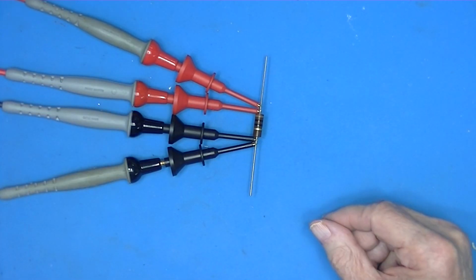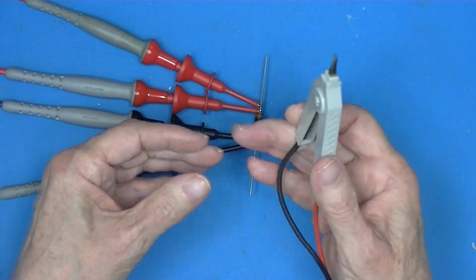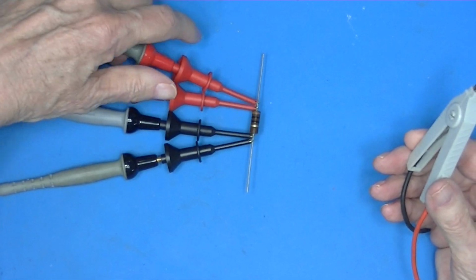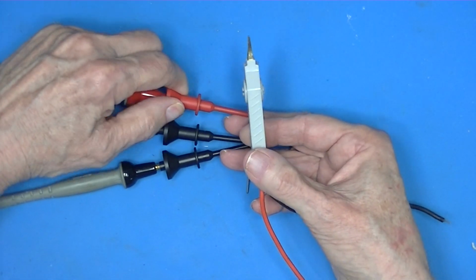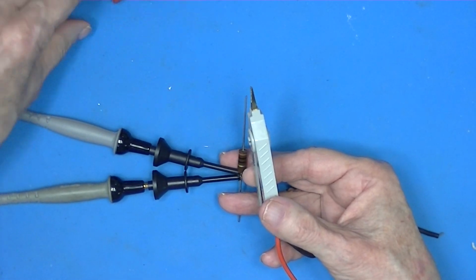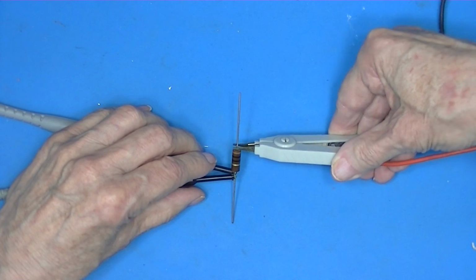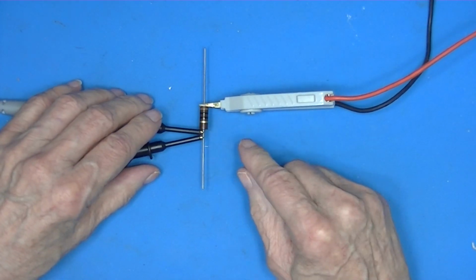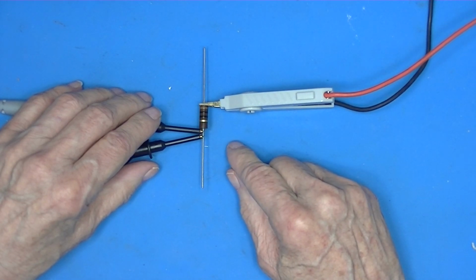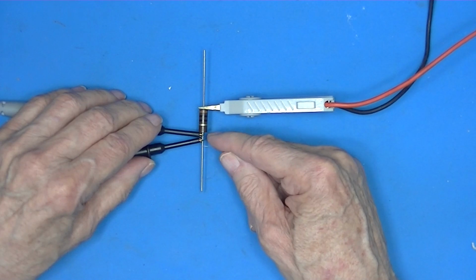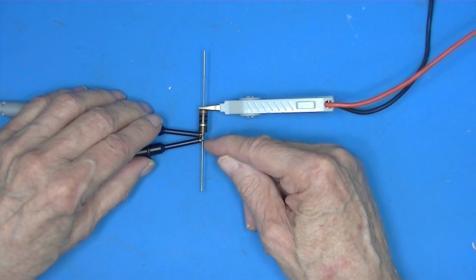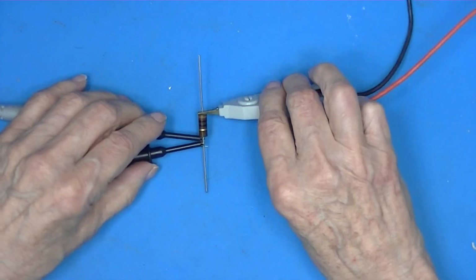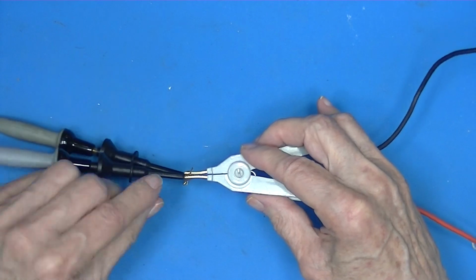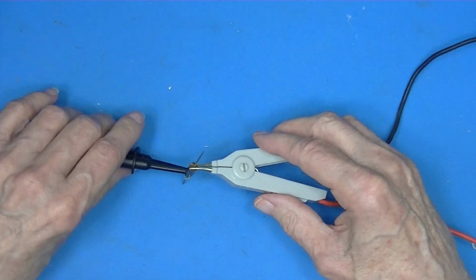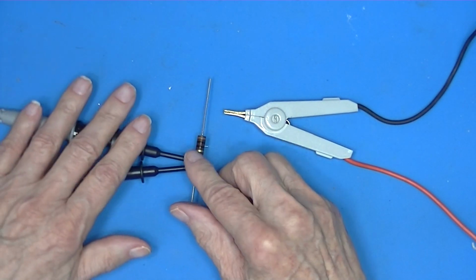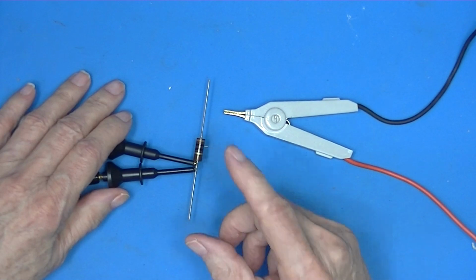In one of the previous videos, I showed how these could be used to replace two wires. So the connection can be made very closely to the device under test. And instead of having some electrical separation between these two connection points, with the clamp, the only electrical separation is the diameter of the wire. So when does a 4-wire measurement become a 2-wire measurement? Keep that in mind.